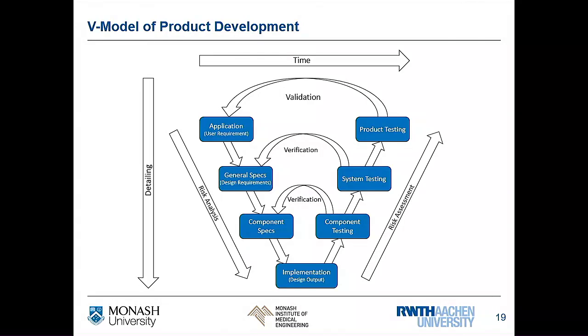And what's important, how much have you been into risk analysis? Have you done stuff like that? Risk analysis a lot? Yeah, also? It's important to understand that for medical devices nowadays, the approval process is more and more for all products linked directly to risk analysis. In former times you said, I have this device, you have to make this and this test, and then you get it approved. If it makes sense or not, nobody cares. Nowadays you get told, this is your device, tell me the risk of your device, tell me how you approached and assessed it, and tell me what you did in order to solve it or to reduce it. So that is very important, and so I can probably go through that.